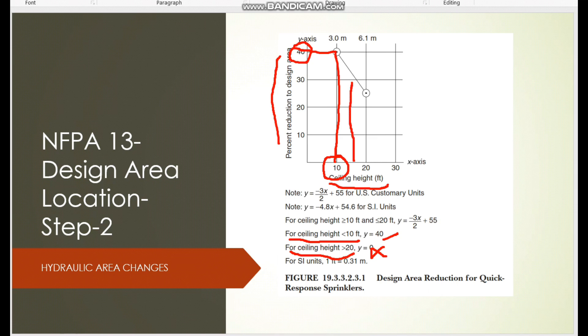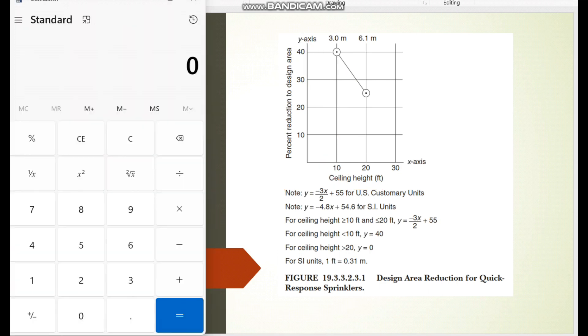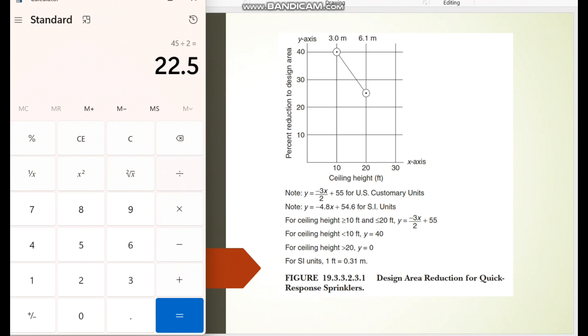For intermediate values, you apply the formula. For example, with a 15-foot ceiling height: take negative 3, multiply x (which is 15) divided by 2, giving 22.5, then subtract that from 55 — that equals 32.5 percent. So for a 15-foot ceiling height you reduce 32.5 percent from your hydraulic area, meaning from 1500 square feet you reduce 32.5 percent for the quick response sprinkler.